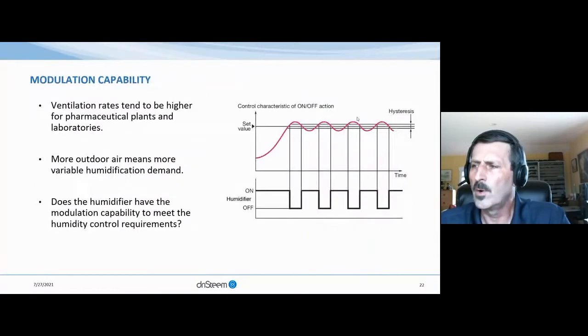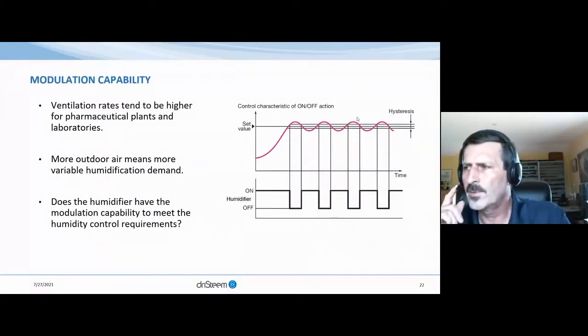A quick word on control. With processes often having variation and higher outside air exchanges, higher accuracy and faster responding systems may be required. DriSteem can provide high accuracy resistive units utilizing solid-state relay technology and state-of-the-art vapor logic controllers. In addition to resistive, high-pressure atomization is also capable of high accuracy and fast response. All of our systems are available with BACnet and other building management protocols to ensure an effective control strategy is achieved.